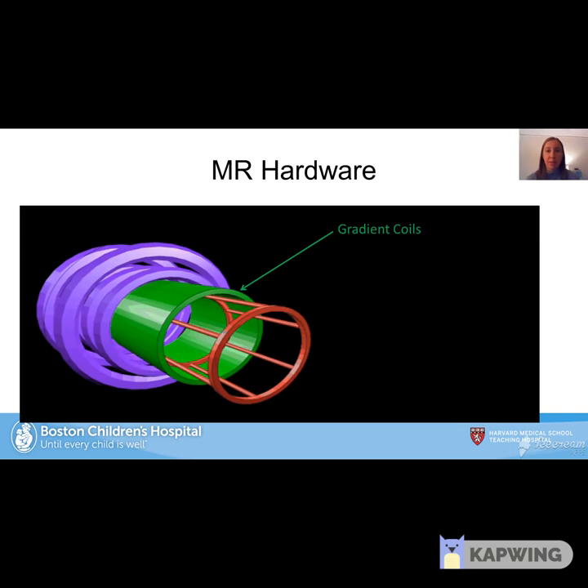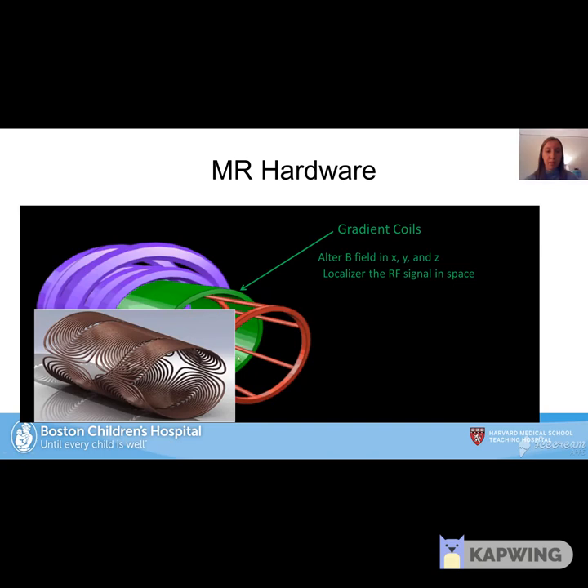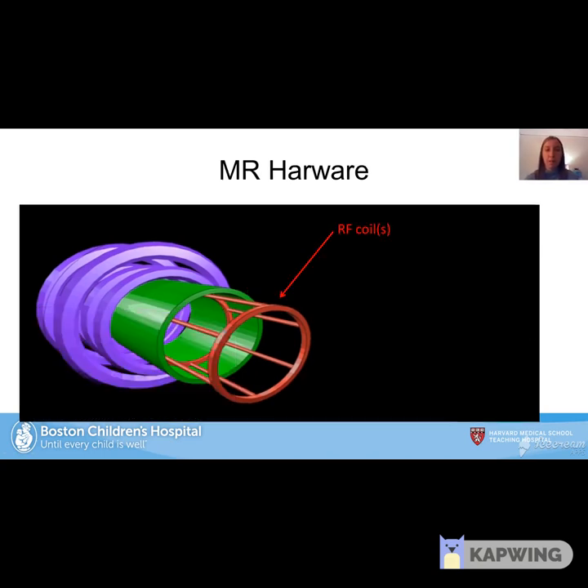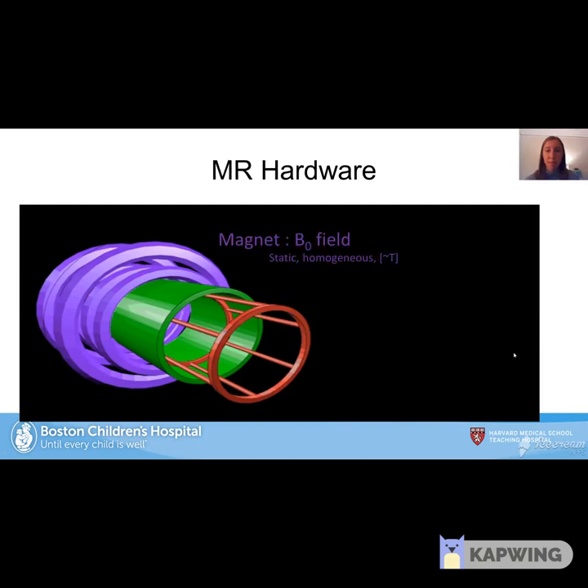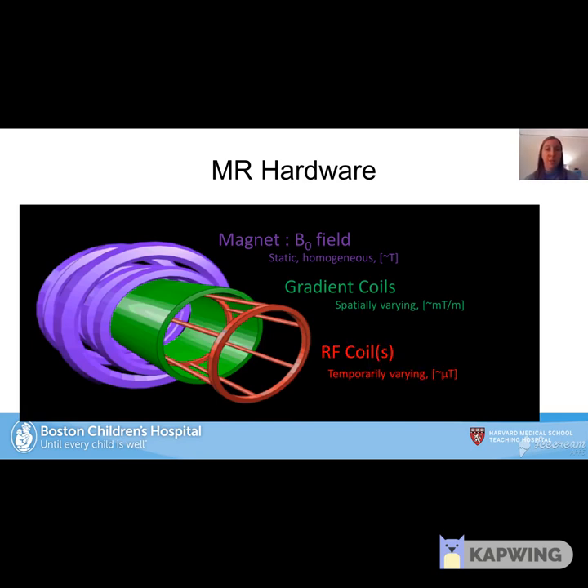The second component is the gradient coil, on the inside of the magnet. The gradient coil alters the magnetic field in the x, y, and z directions and is important for localizing the RF signal in space. The third component is the RF coils, which send and receive RF signals to and from tissues. To summarize: the magnet provides the static, homogeneous B-naught field operating on the order of tesla; the gradient coils are spatially varying at millitesla per meter; and the RF coils are temporally varying at micro-tesla.